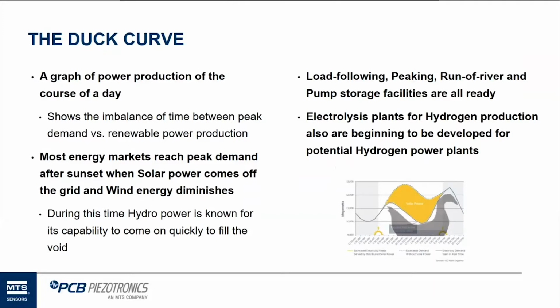So once all this happens, hydro is turned on. And it's known that once this happens, it's basically a switch, and hydro can come on very quickly to fill the void when the other renewable energies have to get shut down. So once they reach the lower part of that curve, all the different types of hydro facilities we talked about, run of the river, dams, pump storage, are all ready to go at this point, providing they're not under maintenance or something like that.